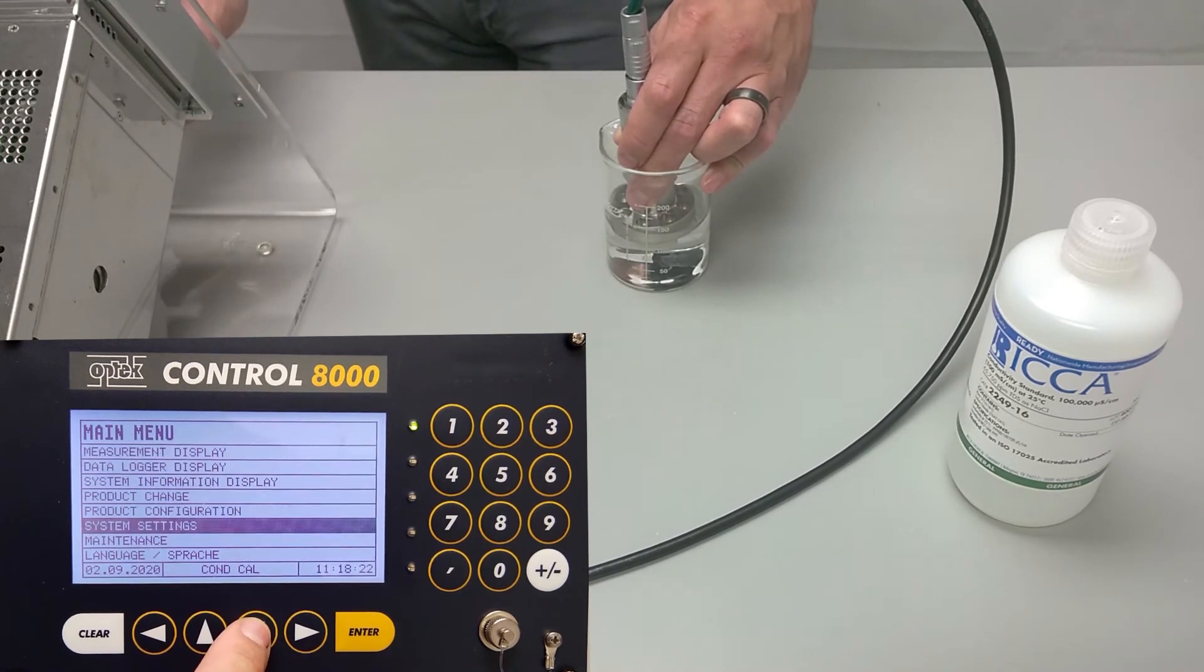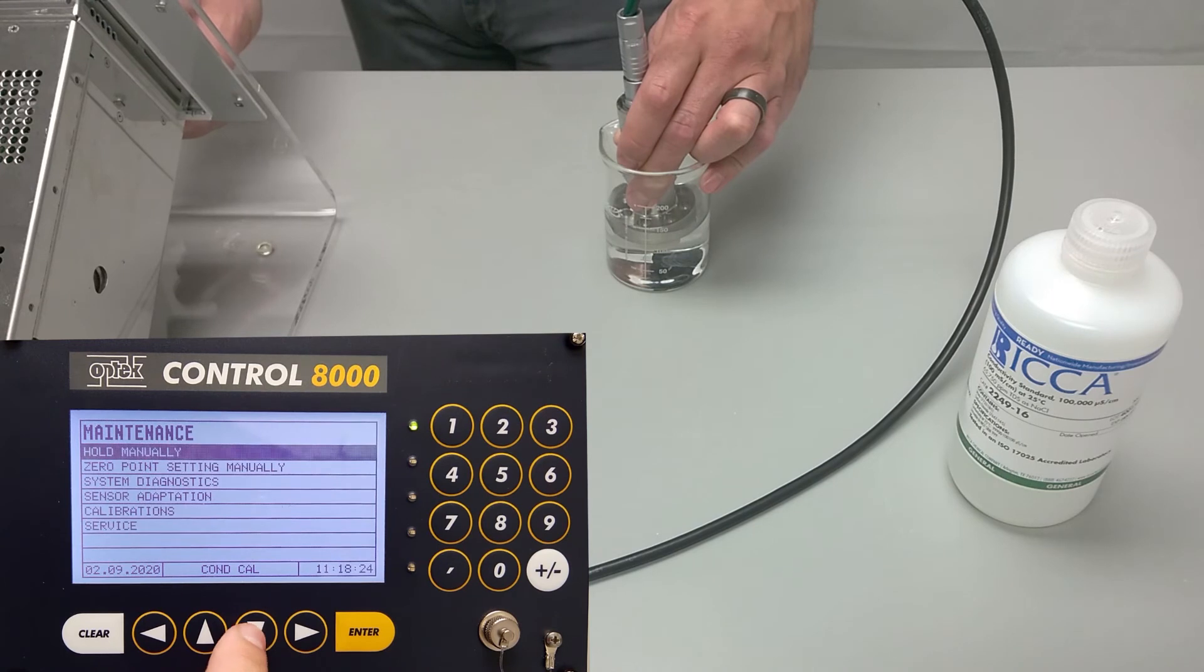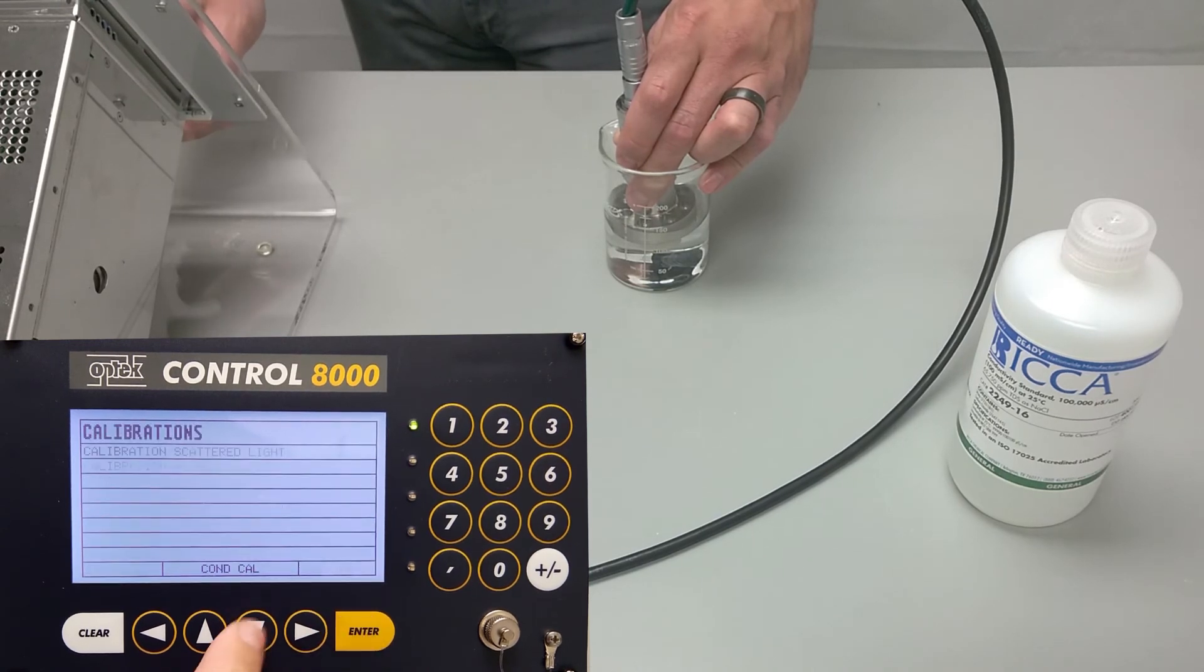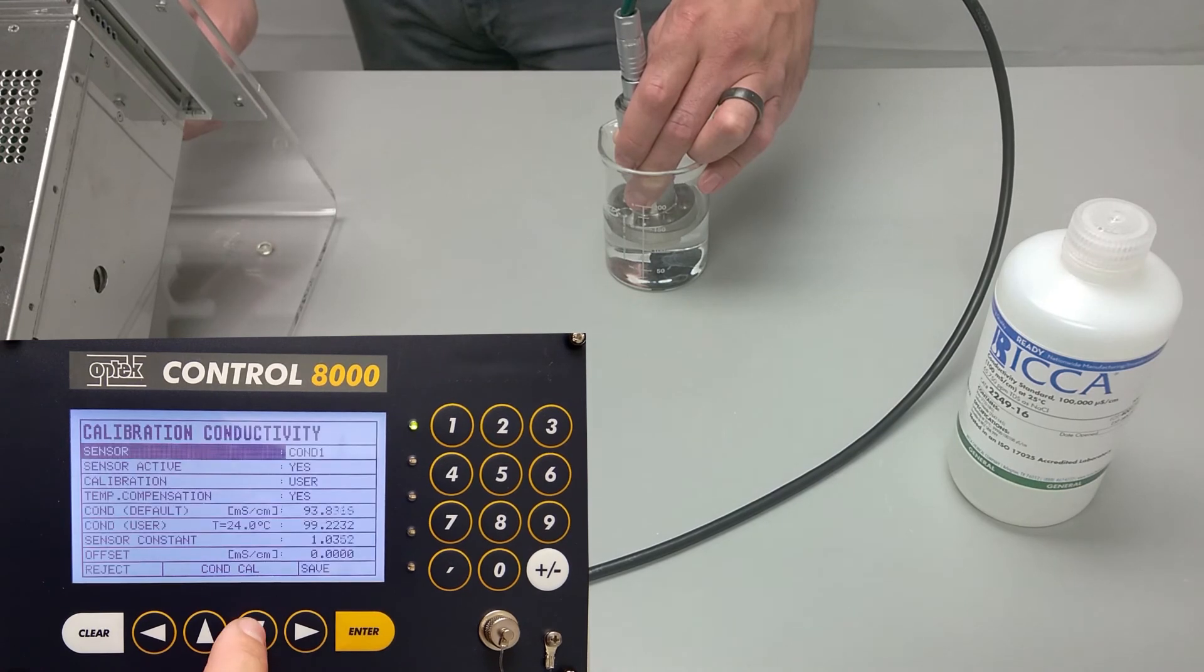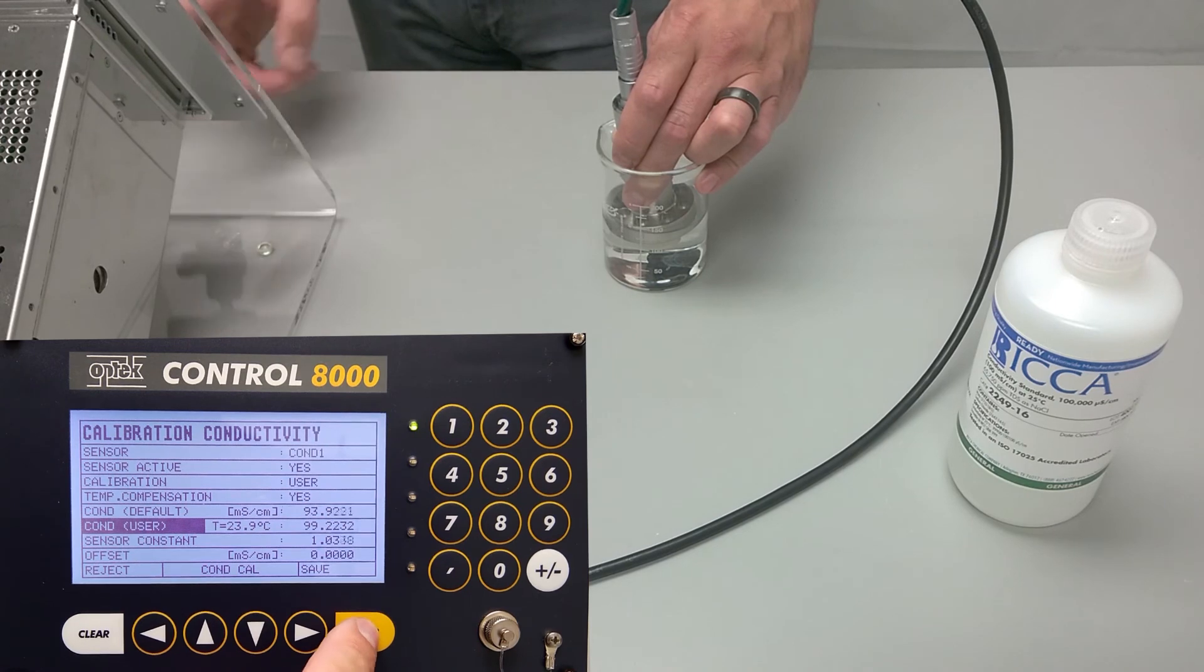We'll scroll down to maintenance, press enter, scroll down to calibrations, scroll down to calibration conductivity auto. COND1 is selected, so we'll scroll down to COND user and press enter.